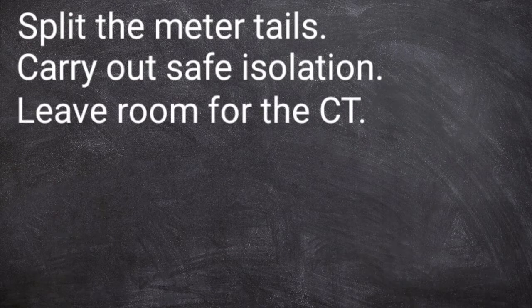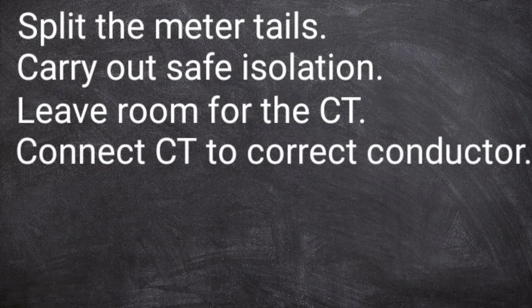We don't want to bury the cable around the back of the other tails to make it very difficult to get the CT on. We want to think about where that's going to end up. And connected to that, we want to make sure that the CT is connected onto the right conductor. So which conductor are we talking here, Gary? You're looking at the line conductor from the outgoing side of the meter. So we've got line and neutral coming in and then neutral and line going out.